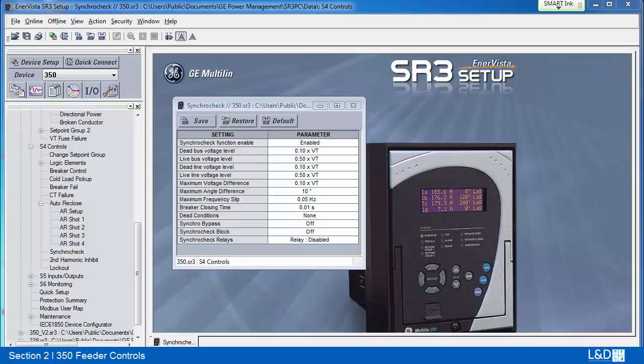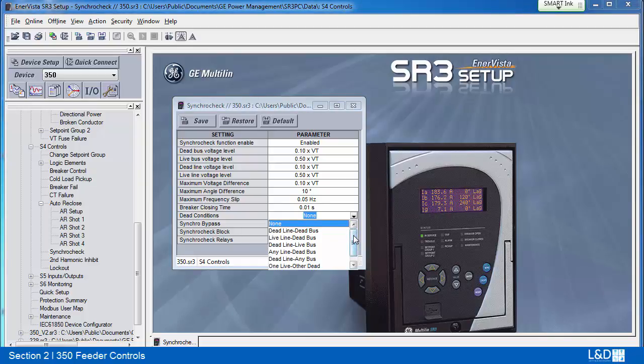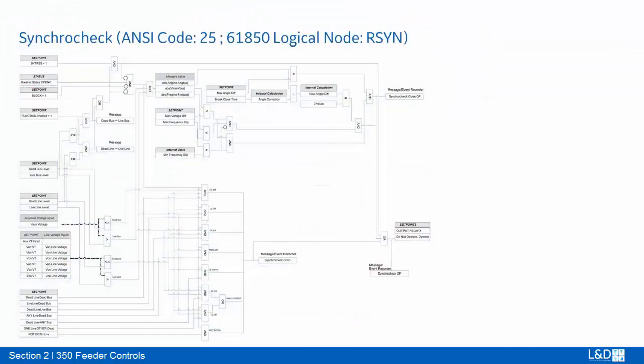If the user wants to enable closing permission for cases where there is a loss of one or both voltages at both ends of the breaker, the synchro-check function incorporates closing permission logics. In the live line-to-live bus case, once voltage difference has been successfully verified in magnitude, the slipping frequency must be checked. If the frequency difference between line and bus voltage is lower than 30 mHz, closing permission is granted. But if the frequency difference is greater than the maximum frequency slip setting, closing permission is not granted.